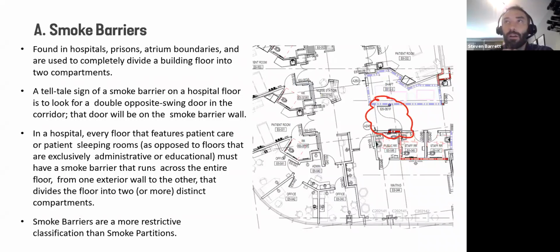So any of you that work on hospitals or prisons, you might have seen a smoke barrier before or an atrium boundary. And these are used to divide floors into compartments. One, you can see in the graphic here on the right, I pulled this from a hospital project. If you see the cross-swinging doors going in opposite directions, that's typically, but not always, a sign of a smoke barrier wall. So the way hospital designs work, every floor that has patient care must be divided into at least one smoke barrier, and that completely cuts across from exterior wall to exterior wall.